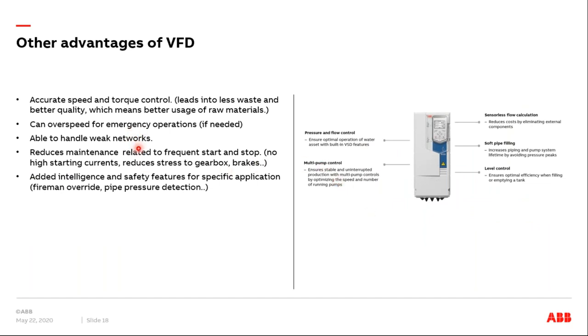When you use a VFD system, you also have better control of your speed and torque. On the industry side, this means you have better quality and less waste of material. If you use an induction machine directly connected to the line, as the load increases or decreases, your slip will change, and that means the speed of your rotor, and actually the end application, would change. That would not bring you good consistency in quality, and you are also wasting material. So it's not just the energy side, but also the quality side where you have a benefit.